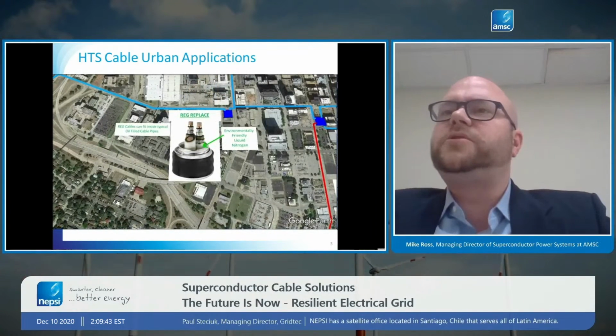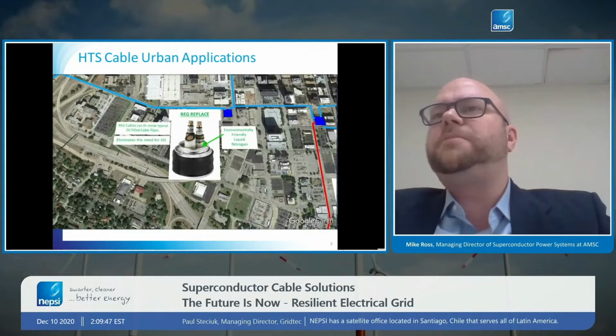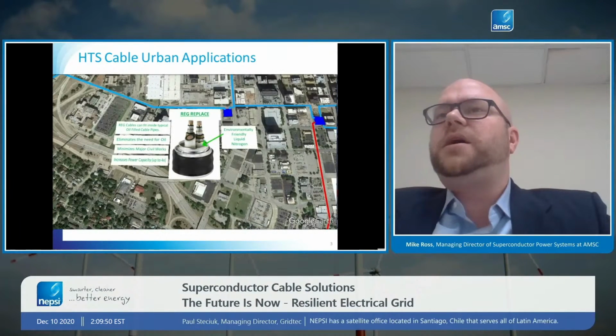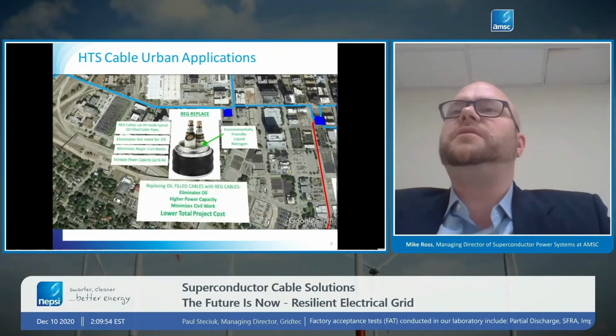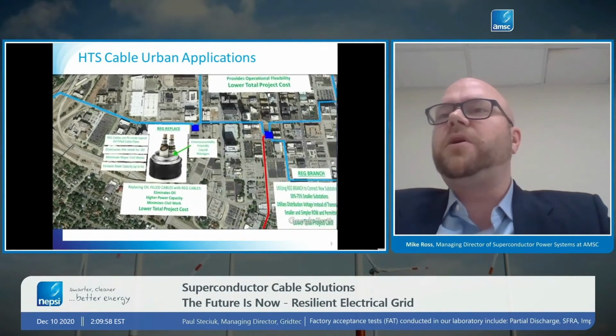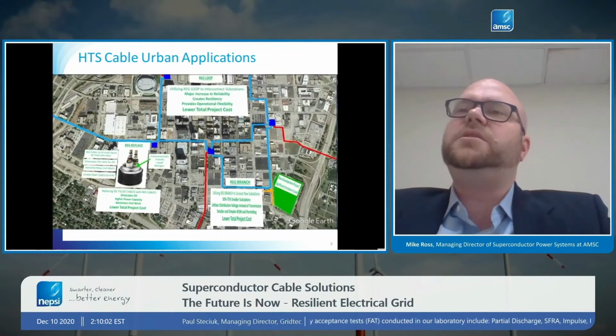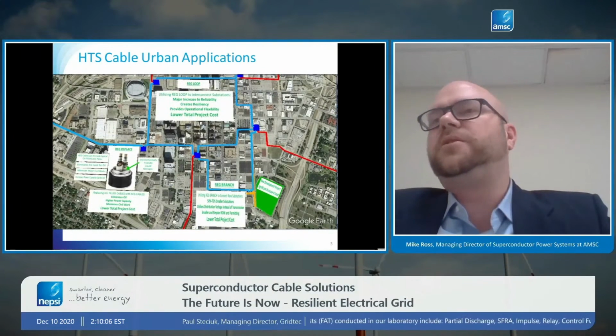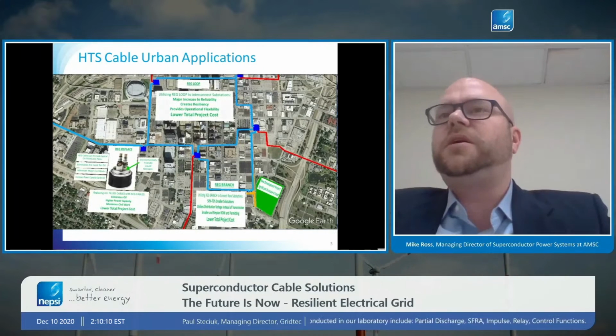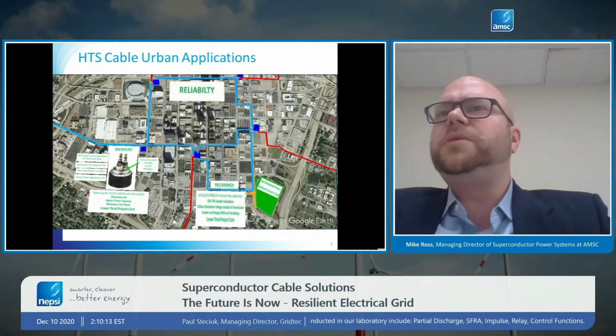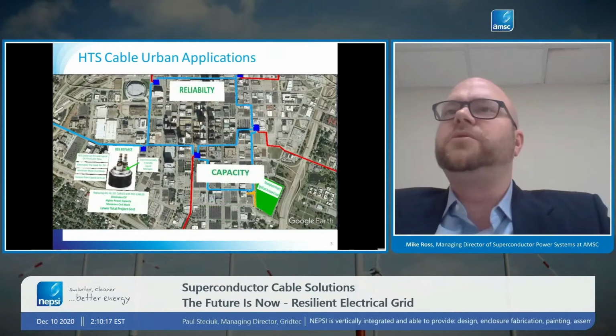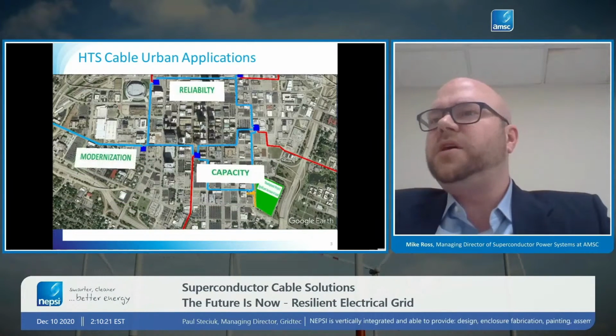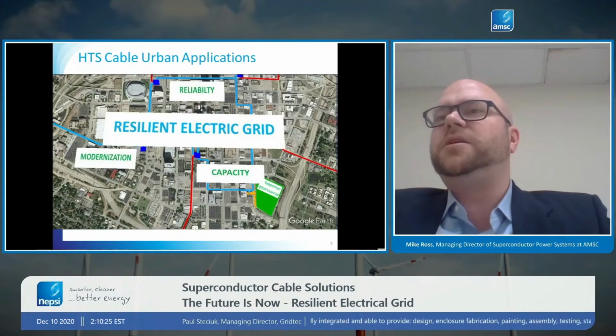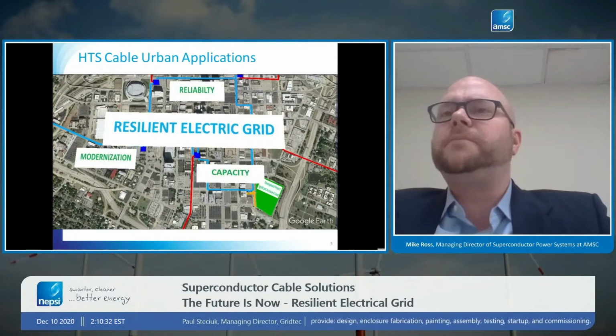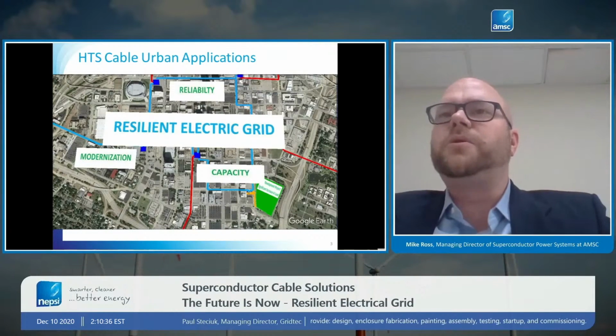So another application of superconductor cables is to replace these pipe-type or oil-filled cables with superconductor cables, and we'll find that the installation of these cables and the coolant that's being used, which is liquid nitrogen, is far more environmentally friendly and minimizes the amount of civil works and disruption that would go into a project like replacing those pipe-type cables. So those are the 3 main applications that we're gonna touch on today. Again, improving reliability in these loop-type applications, improving load serving and capacity in the branch-type applications, and then modernizing the grid. And what we like to say is that the combination of improving reliability, capacity, and bringing up things to modern technologies is how you create a resilient electric grid.